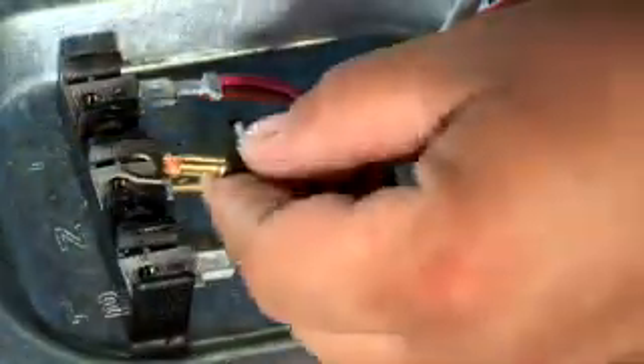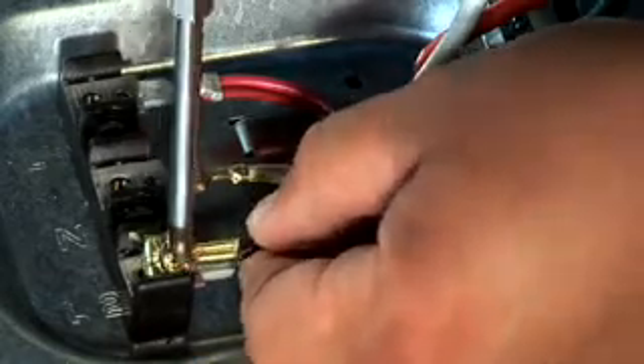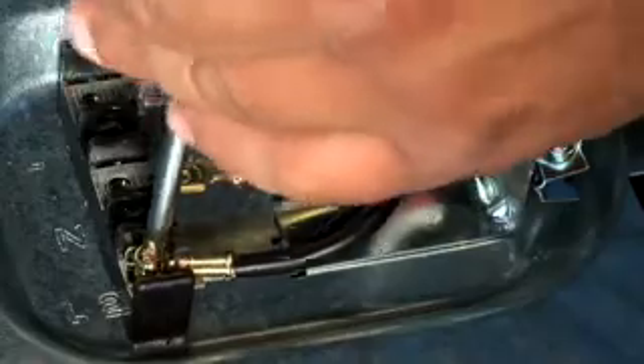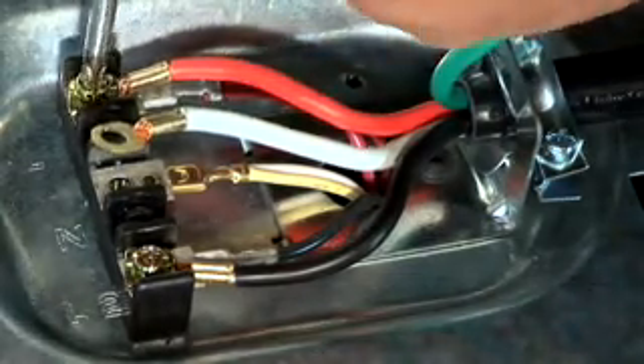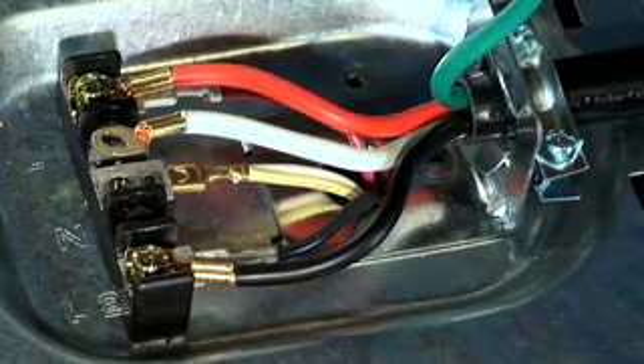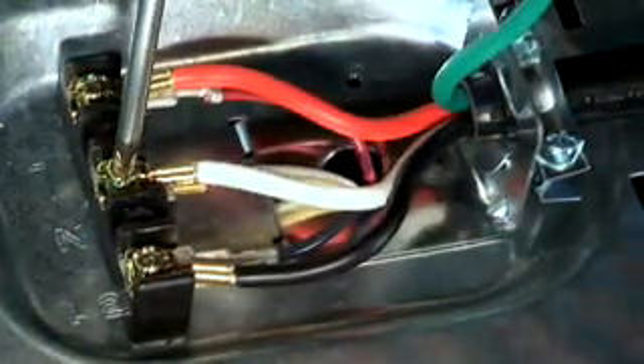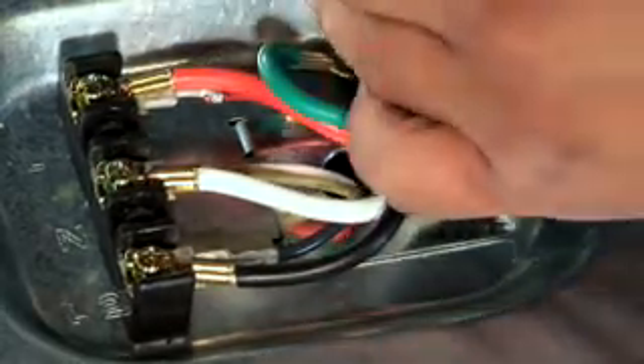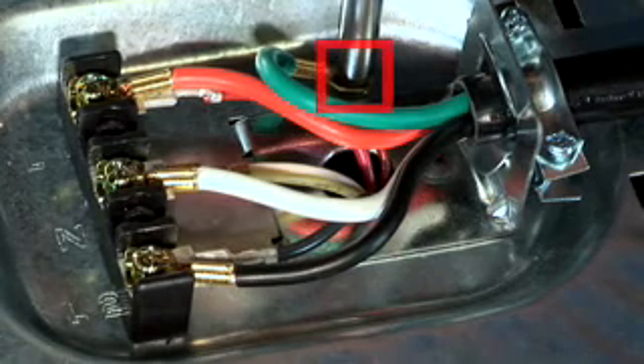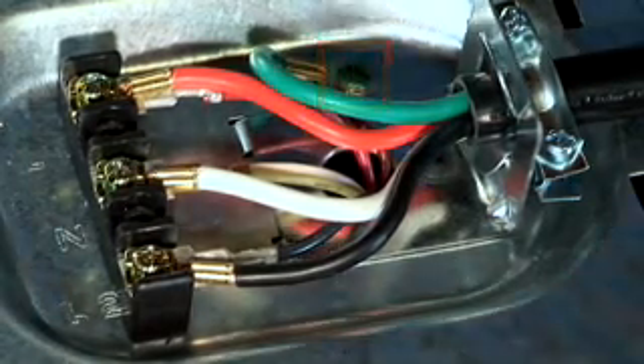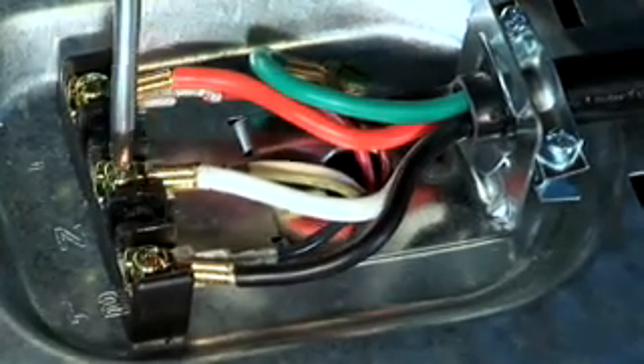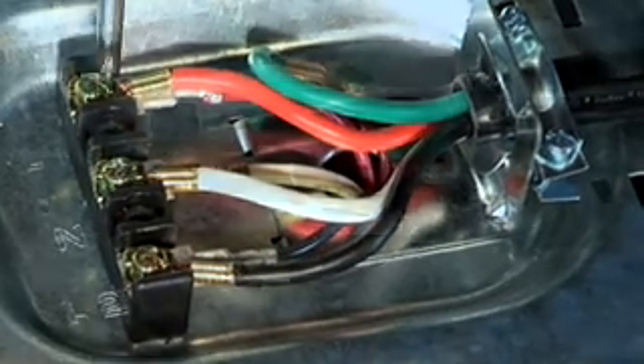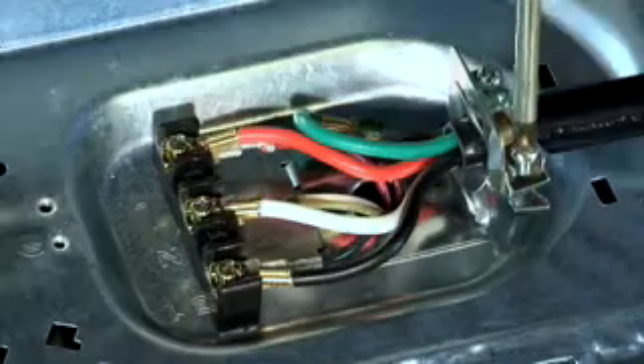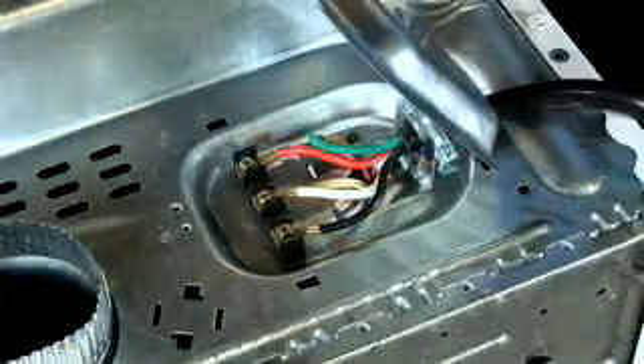Connect the power cord as follows. Connect the 2 hot lines to the outer screws of the terminal block. Then connect the neutral line to the center of the terminal block. Attach the ground wire of the power cord with the green ground screw. Tighten all terminal block screws completely. Properly secure the power cord to the strain relief. And finally, reinstall the cover.